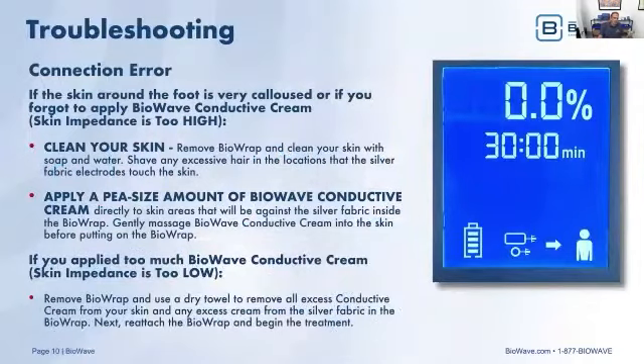A couple of troubleshooting tips. If there's a connection error, your device will show, as in this image here, two pads with an arrow to the body. The pads to the body error icon is basically telling you that the device doesn't see the pads on the body, even though you're all hooked up. The device is hooked up to the cable, to the BioWrap, to the foot. If you see this error condition, it means one of two things: either the skin impedance is too high or the skin impedance is too low.